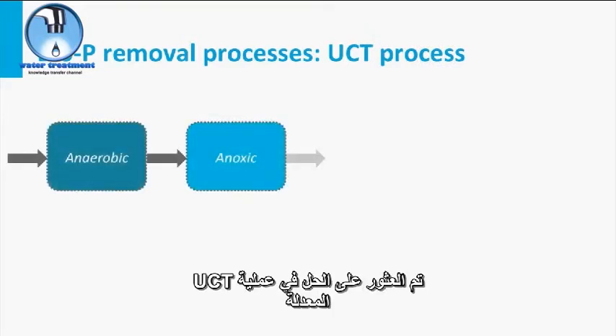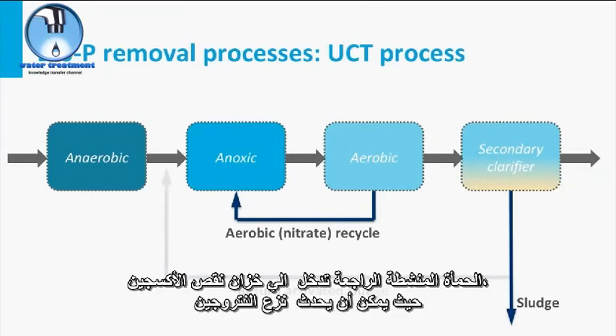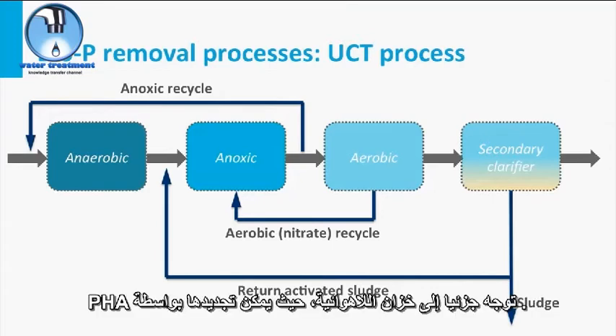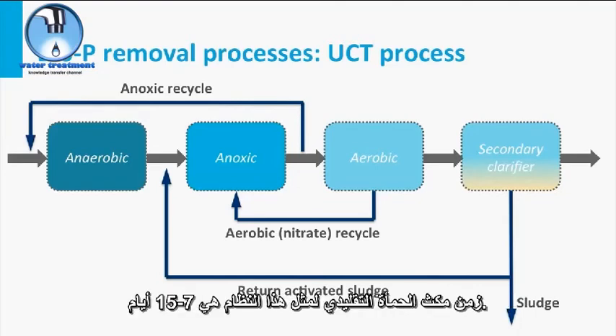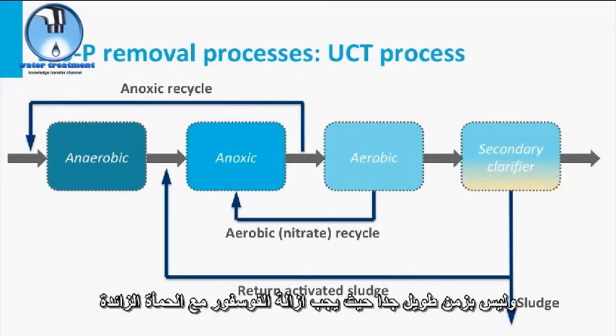A solution is found in a modified UCT process. The return activated sludge is introduced in an anoxic tank, where denitrification can take place. The mixed liquor after denitrification, thus with low nitrate concentrations, is partly directed to the anaerobic tank, where it can be replenished with VFA. Typical sludge retention times for such systems are 7 to 15 days — not too short, since PAO are relatively slow growing, as well as the required nitrifiers, and not too long, because P needs to be removed with the waste activated sludge.